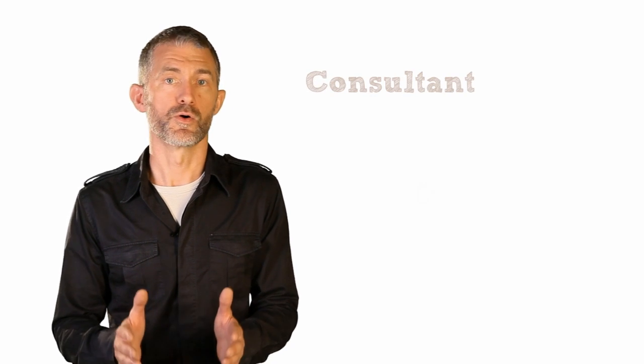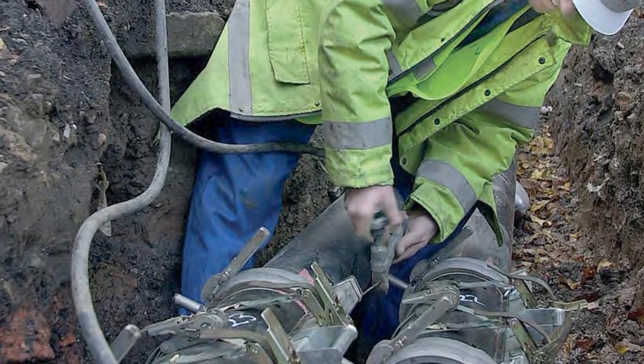If you don't already have a district heating system, then you'll need the help of a consultant or contractor who could also deal with the engineering works required to dig the trenches, lay and insulate the pipework, and connect up each building to a heat exchanger and heat meter. This might sound like such a lot of work, and it's hard to see how the economics can be feasible. Indeed, in some cases, it won't be, especially if you are on mains gas already, which is quite cheap at present, or if you have very long pipes running between buildings.